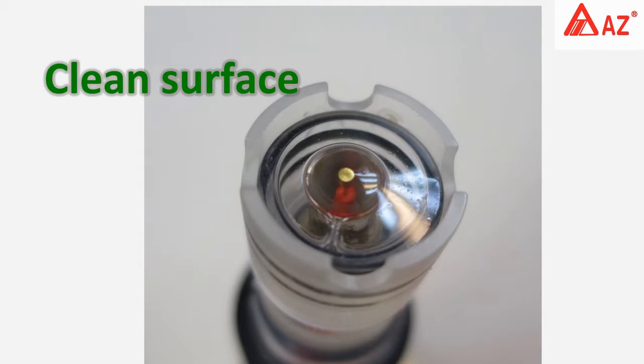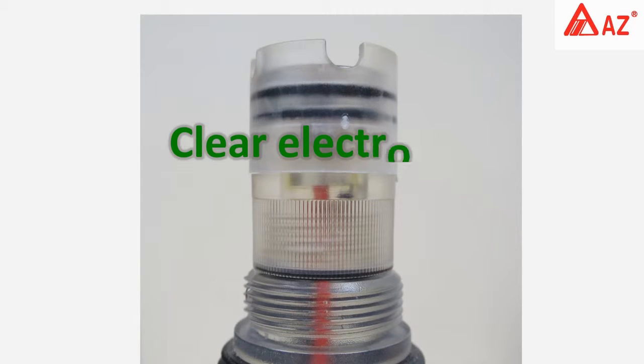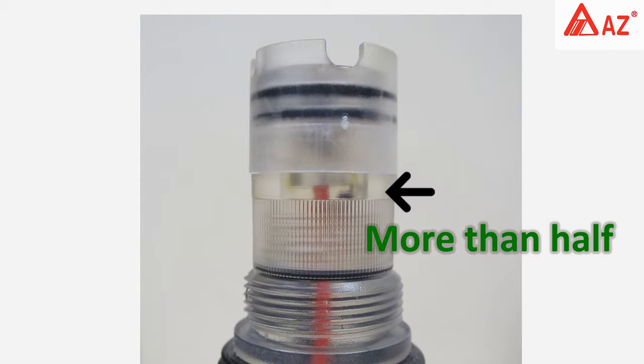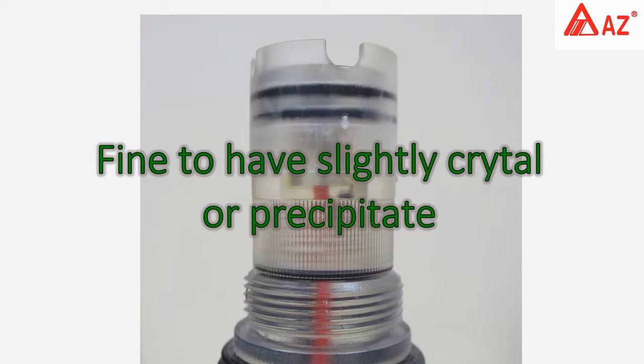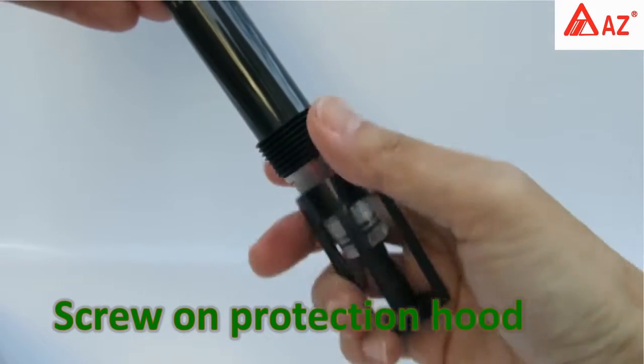The surface of the electrode working area should be clean. The electrolyte should be clear and more than half height. It's fine to have slight salt crystals or precipitate. Screw on the protection hood after inspection.